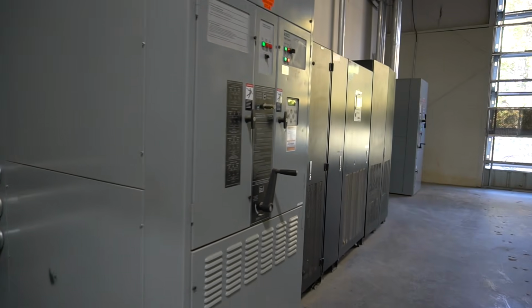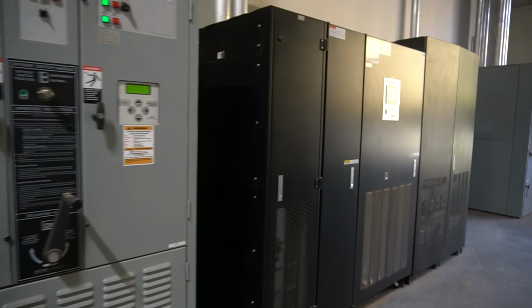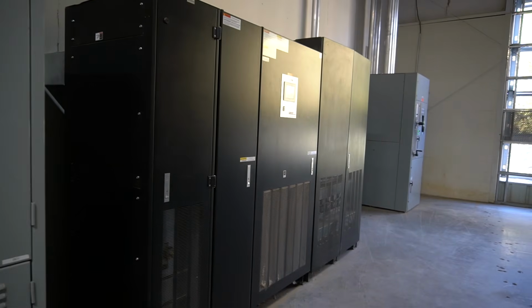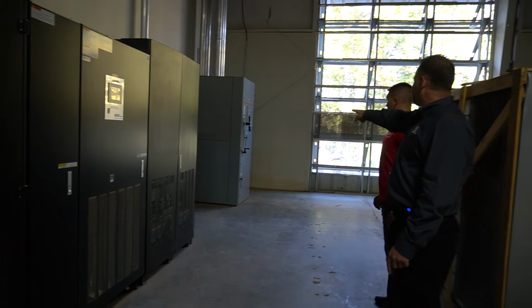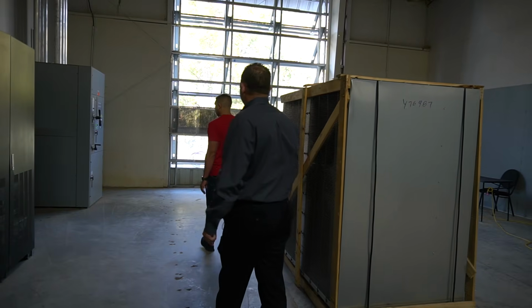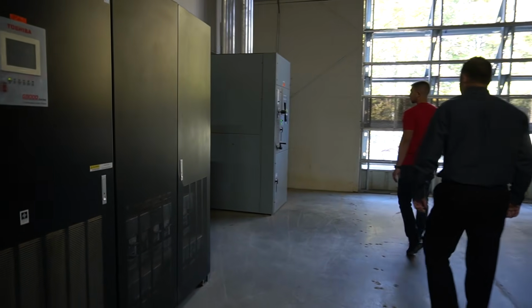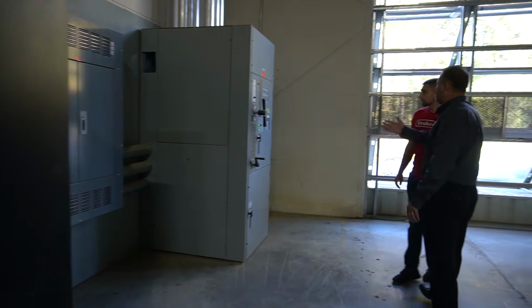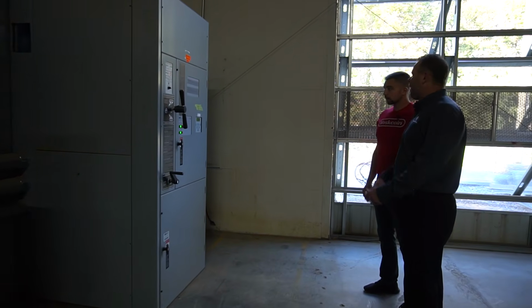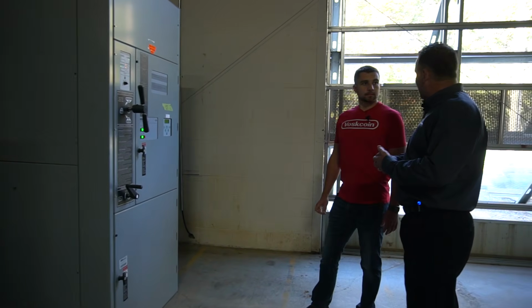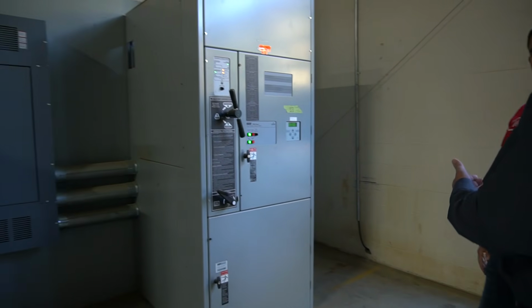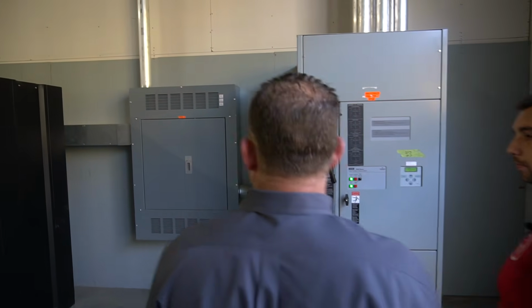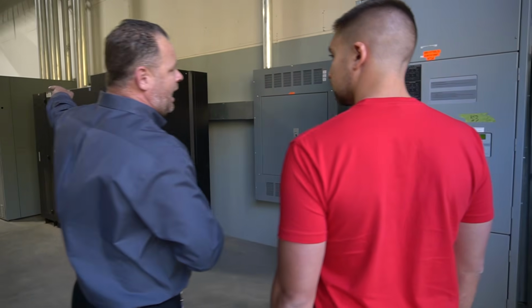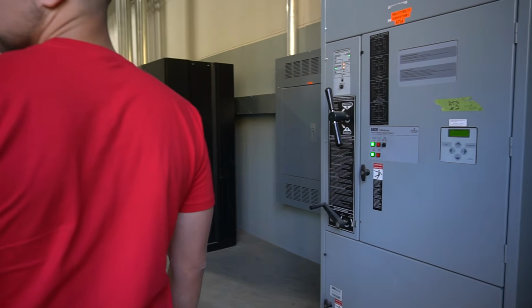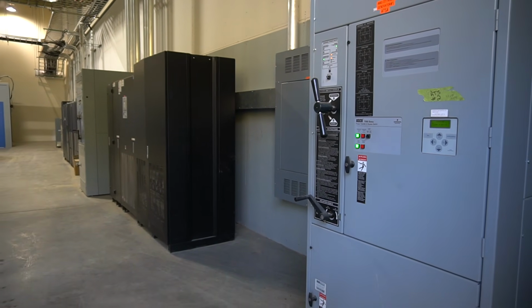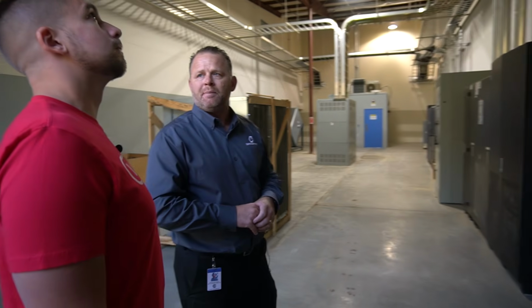So what you saw out back is the two 600 kW generators. One of those feeds this transfer switch, so that in the event that we had a utility power outage, this is major power, right? So this guy's job is to sense utility power. Utility power drops for any reason out there, lightning strike, utility substation goes down for any reason, the UPS will hold the entire aisle while the generator fires up, and then the ATS will kick over, and then the entire aisle will be backed up by that generator.